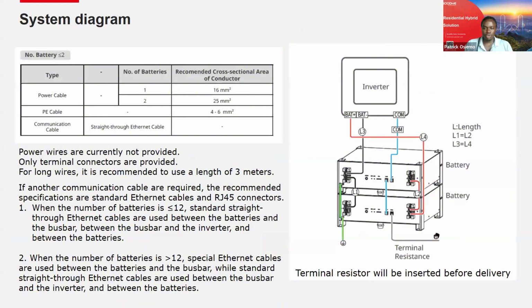Connection wise, you can't connect the battery to the inverter without a combiner box. GoodWe does come with a battery combiner box. So that's the connection scenario. Just paralleling the batteries and the communication, with the last battery having a terminal resistor, and the inverter communicating with the first battery in the loop. And just to be on the safe side, we ensure that the batteries are actually grounded, similar to the inverter.